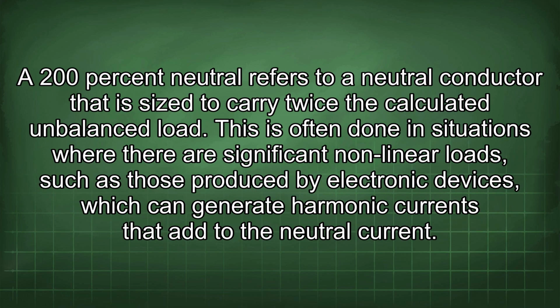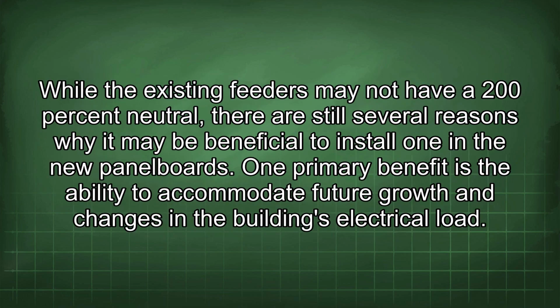A 200% neutral refers to a neutral conductor that is sized to carry twice the calculated unbalanced load. This is often done in situations where there are significant nonlinear loads, such as those produced by electronic devices, which can generate harmonic currents that add to the neutral current. While the existing feeders may not have a 200% neutral, there are still several reasons why it may be beneficial to install one in the new panel boards.